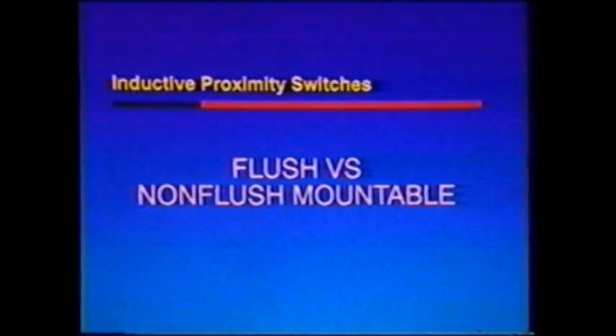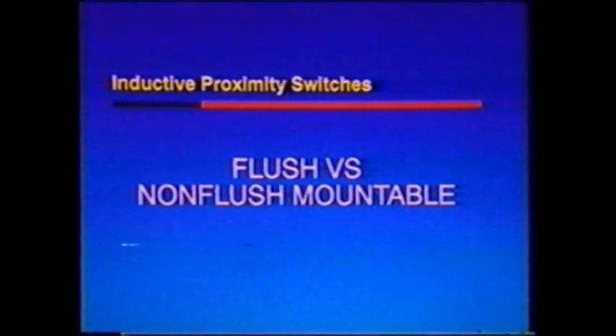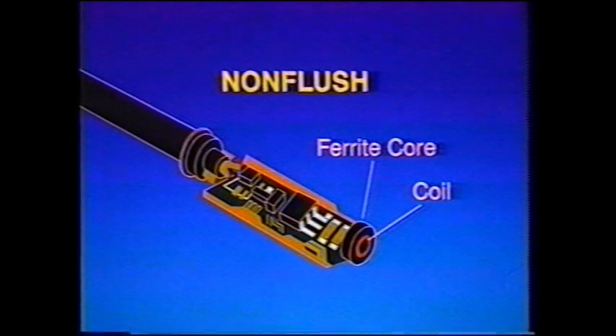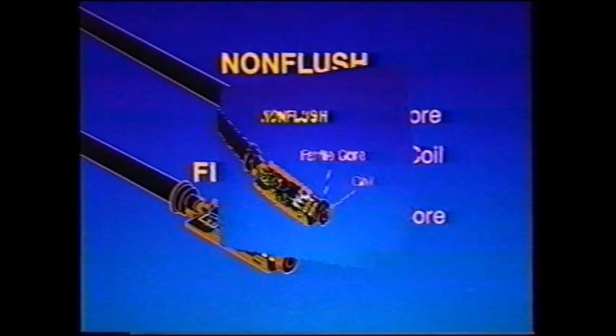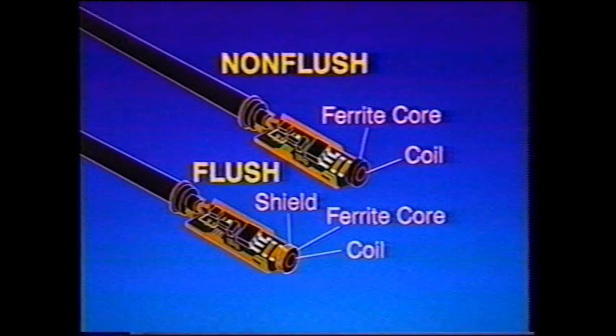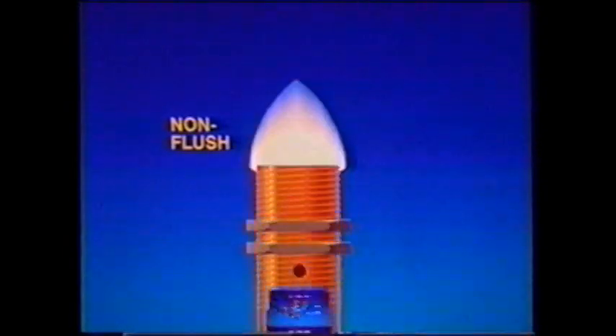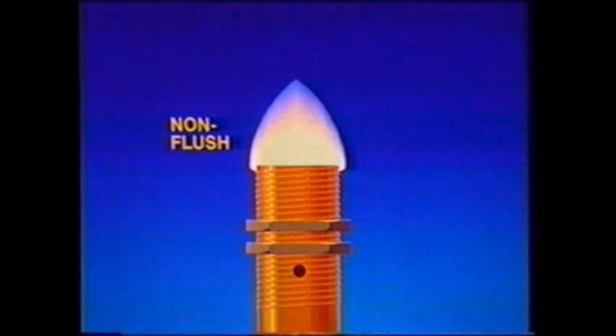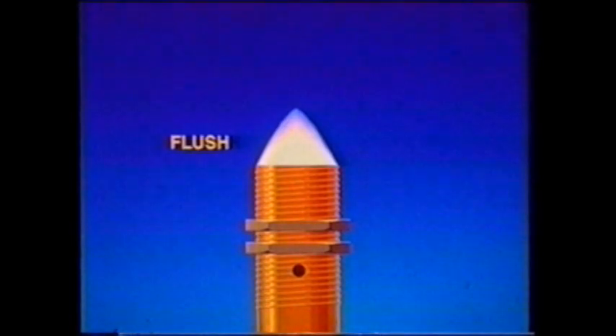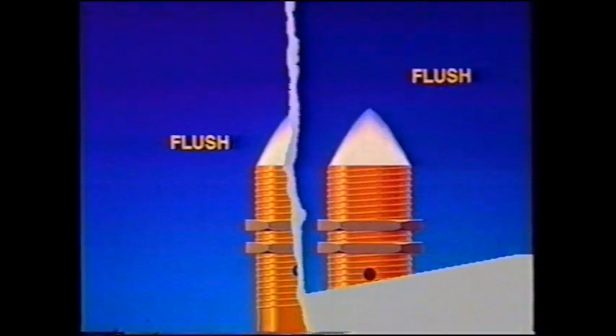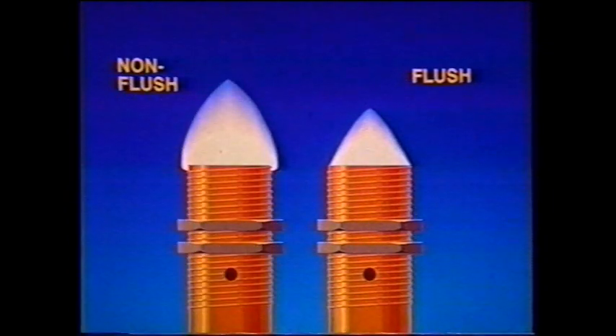In addition to the nominal sensing range, the manufacturer will specify whether a proximity switch is flush mountable or non-flush mountable. An inductive switch contains a coil and ferrite core, which produces a low energy oscillating electromagnetic field. Some switches also include a magnetic shield, which surrounds the core. Proximity switches without the shield — non-flush mountable switches — have a relatively wide sensing area that extends beyond the sides of the switch. The shield shapes the electromagnetic field and produces a narrower sensing area. The shielded or flush mountable switch also has a sensing range which is 25 to 50 percent shorter than a non-flush unit of the same size.